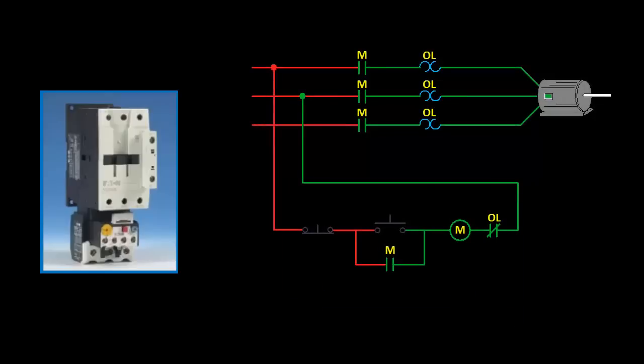To reset the contacts after a trip, we can have it set to either manual or automatic mode. If we have it set to manual, then the reset button on the overload would have to be pressed first, and then the motor can be restarted by pressing the start button.